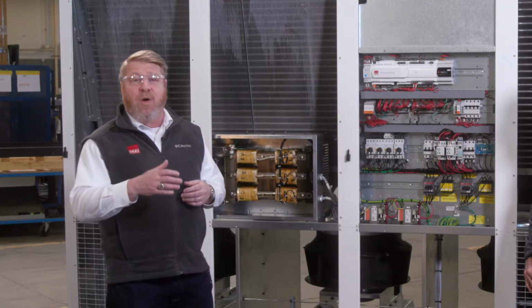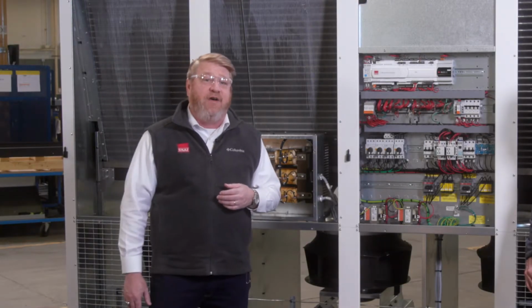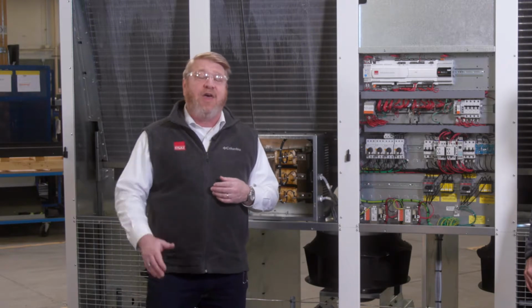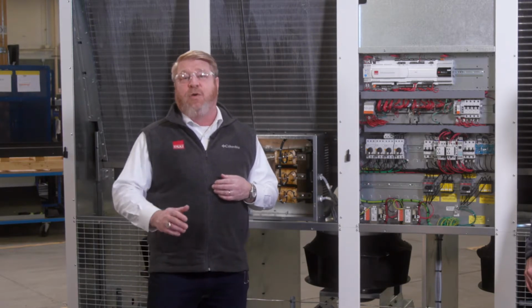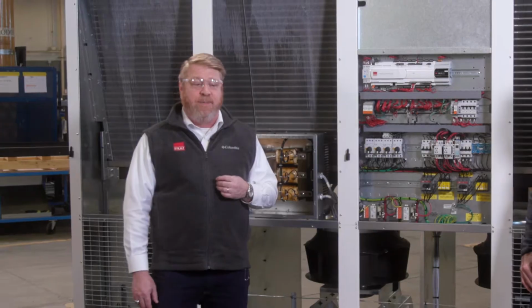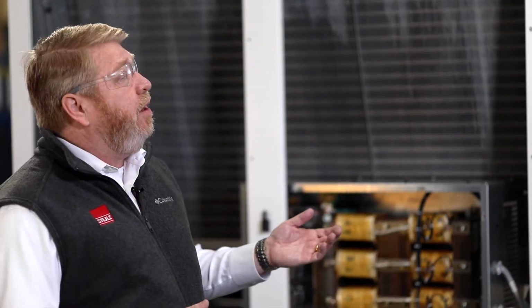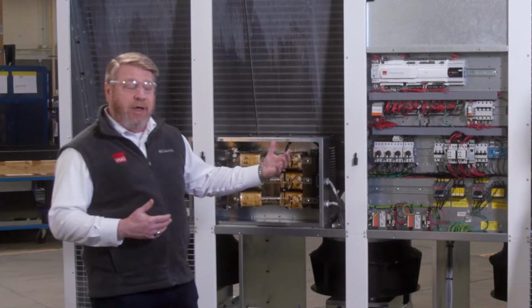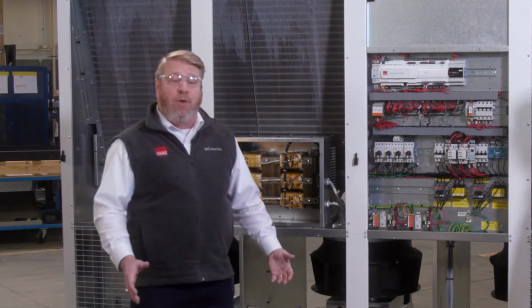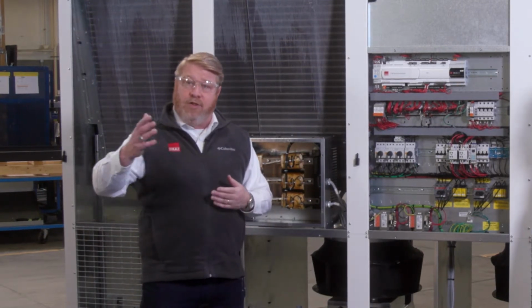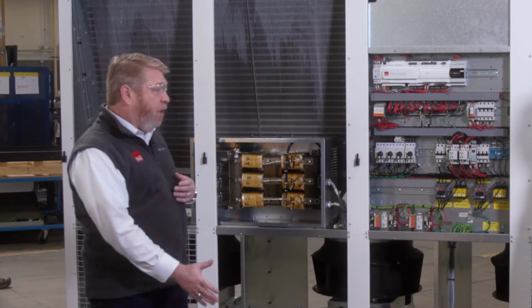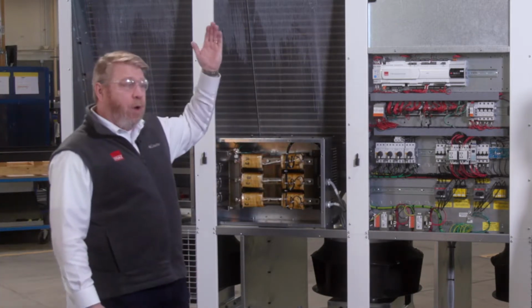If we take a look at the airflow that we can get out of these boxes, it goes all the way from 1,150 CFM to over 90,000 CFM at 0.2 inches of static pressure. The boxes come in multiple configurations. We have a standard downflow, which is the air coming through the top of the unit and then exiting into the raised floor. We also have an upflow where the airflow comes into the front of the unit, goes through the cooling coil, and then exits out the top into a plenum.